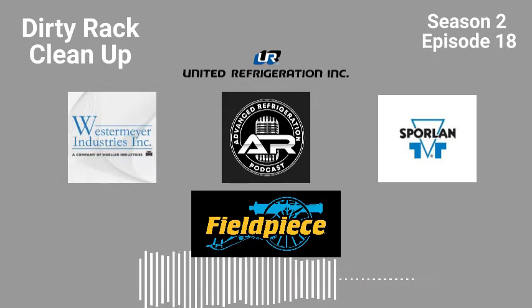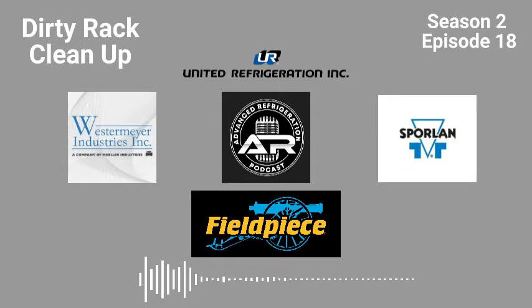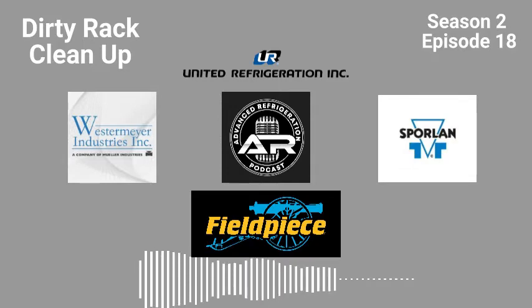Well, hold on. This is on the flash tank bypass. So technically, you could use a conventional CDS valve, right? That's what I did. I took a Sporlan CDS valve, which has almost the exact same specs as this ETS valve, almost to a T. The CDS valve had like a 40-pound higher working range, and I ended up slapping that on there against the manufacturer's wishes, because they told me it wouldn't work and it would fail. Lies. Yeah. They offered zero solutions, only negativity.